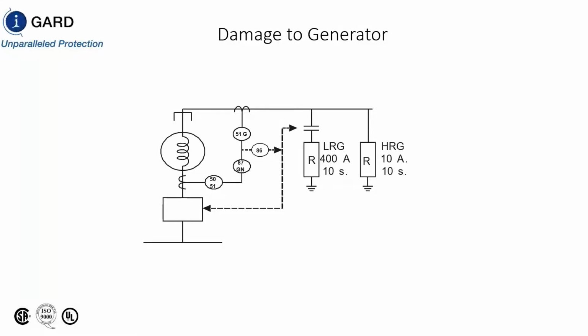So you can see here the differential protection detects the ground fault within this zone. And if you have a ground fault anywhere in this zone, you open up the main breaker, open up the vacuum contactor, which isolates the low resistance ground in the system and allows the generator to coast down with a high resistance ground in the system. So 10 amp, and it doesn't need to be rated continuously. It's a 10-second resistor.